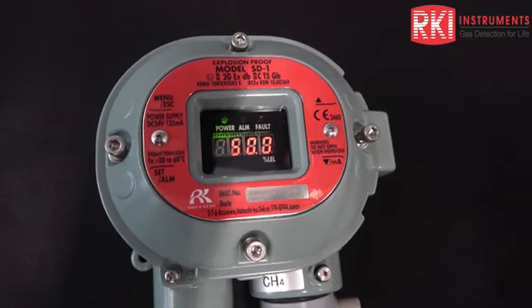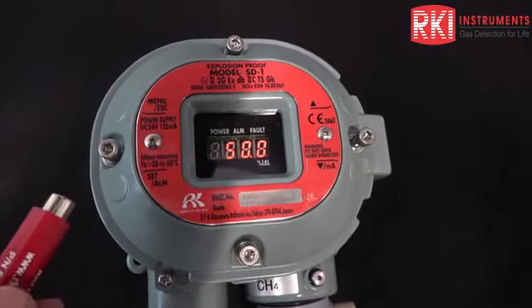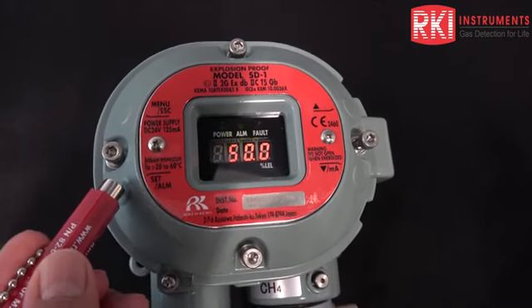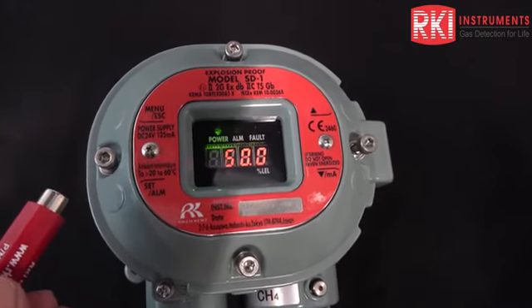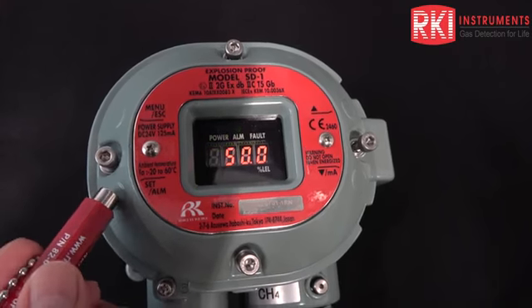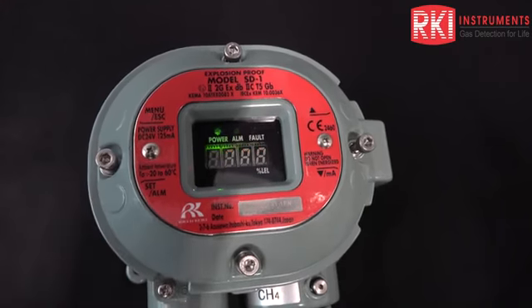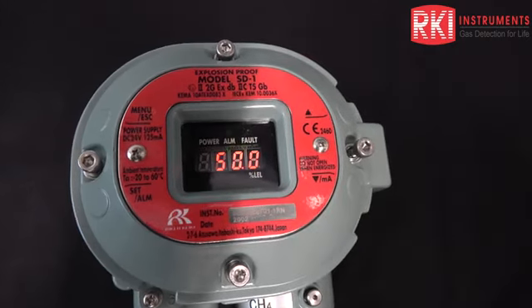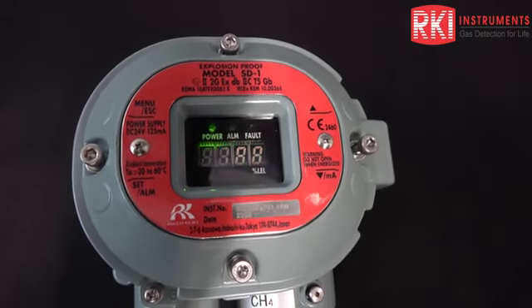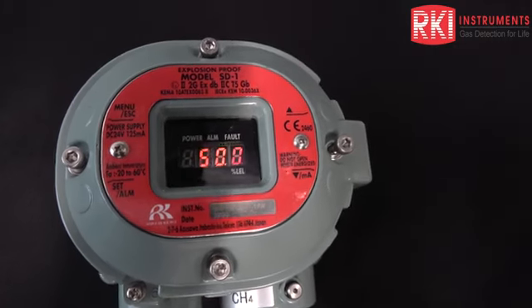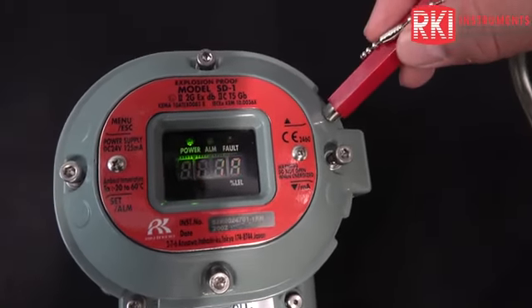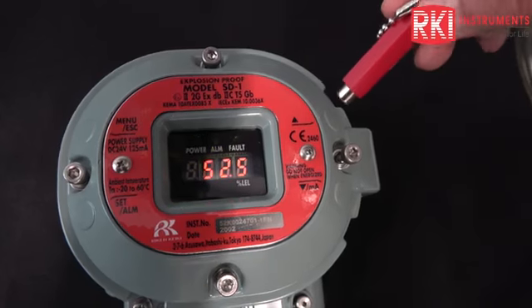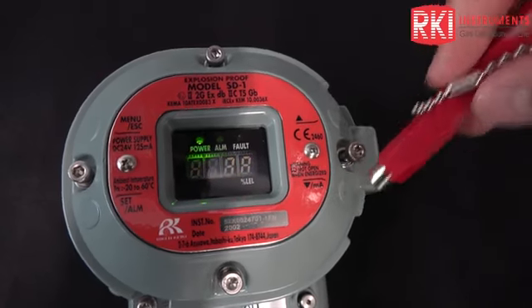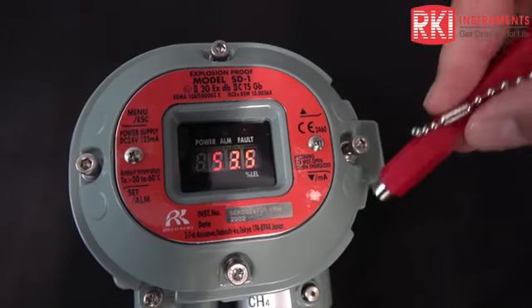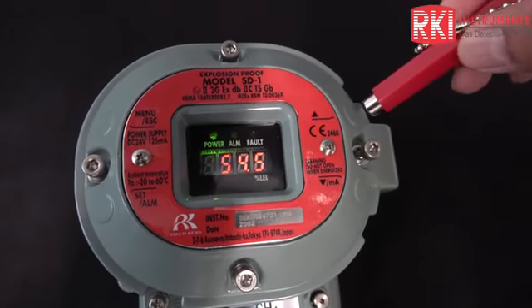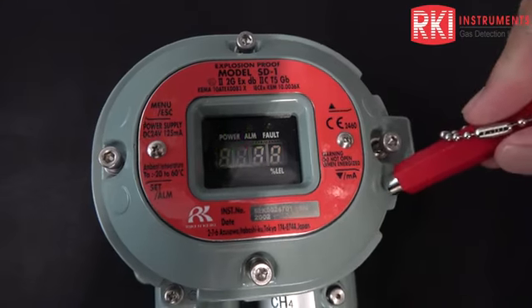What we would do then is we would hit the set pad again once the read is stabilized. And what I want to do is I want to get that reading to flash. Okay, now it's flashing. So what you want to do is you want the instrument to acknowledge where it's stabilized at, and then you'll use the up and down pads to change the value to what it really should be. All right, so if I had been down at 40, then once it's flashing, you can go up or down to get it to 50, which is what I'm calibrating with, 50% LEL hydrogen. So I'll take it to 50.